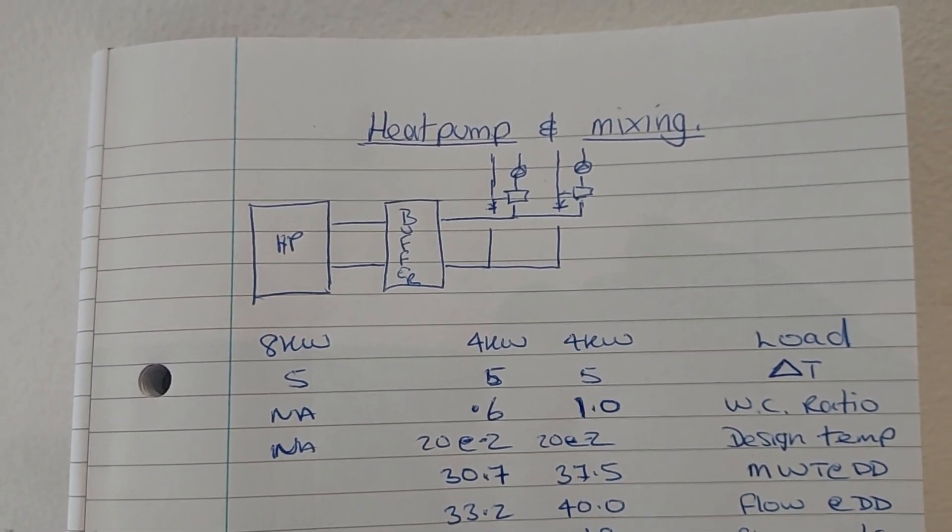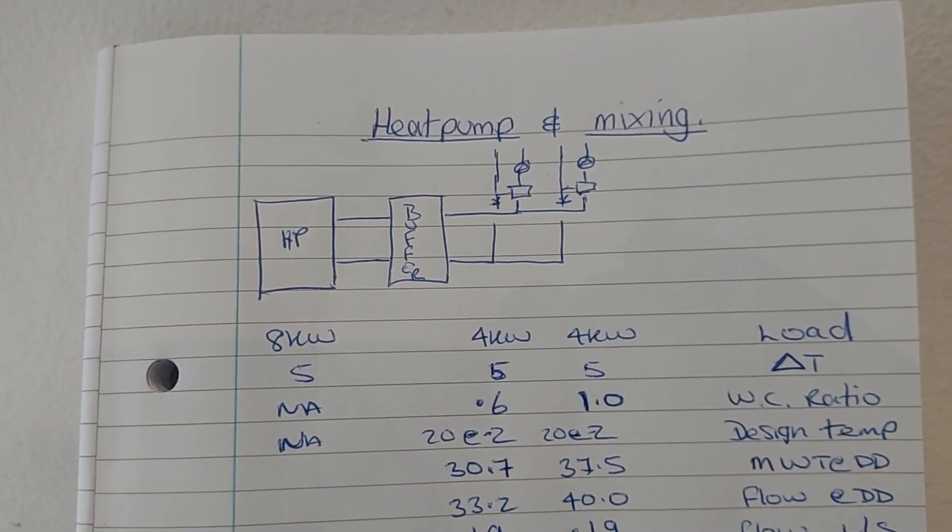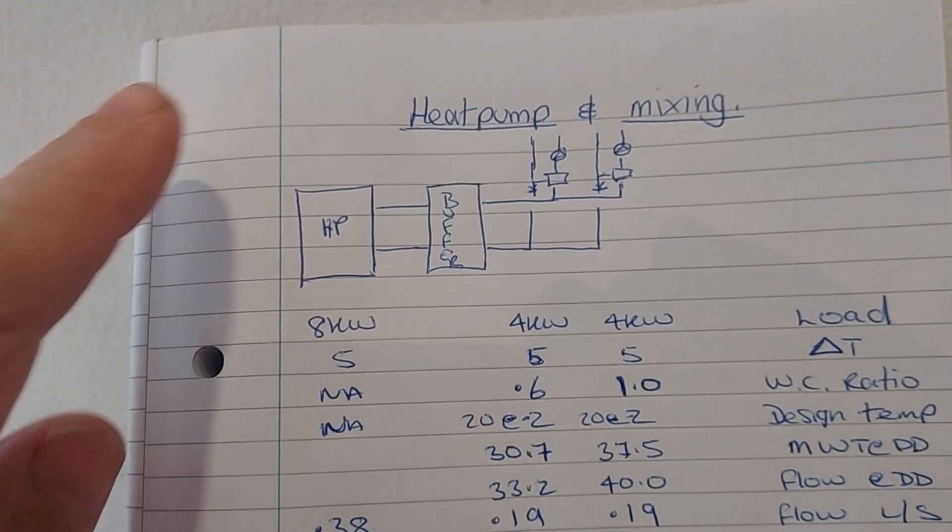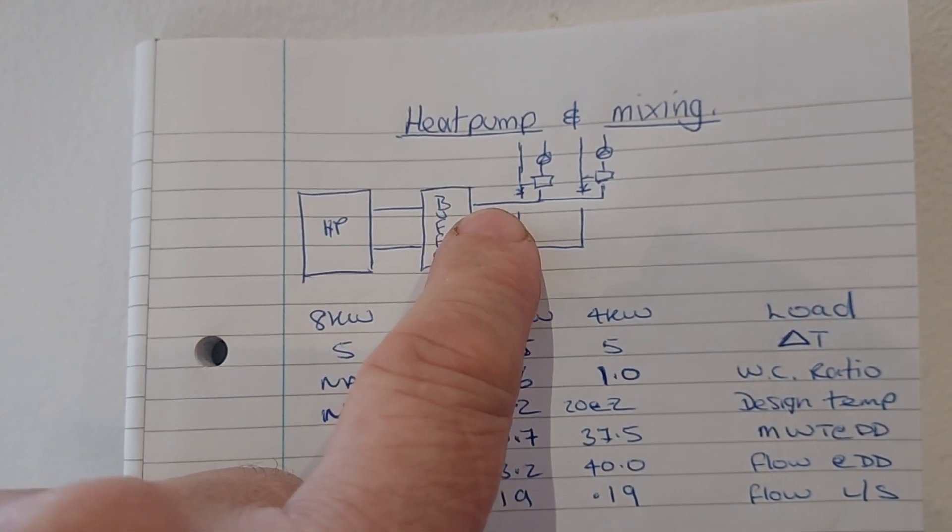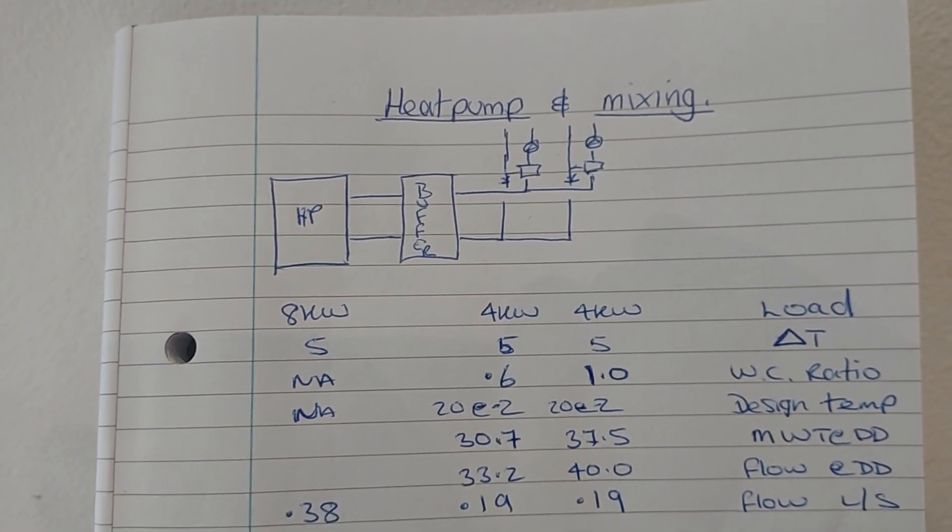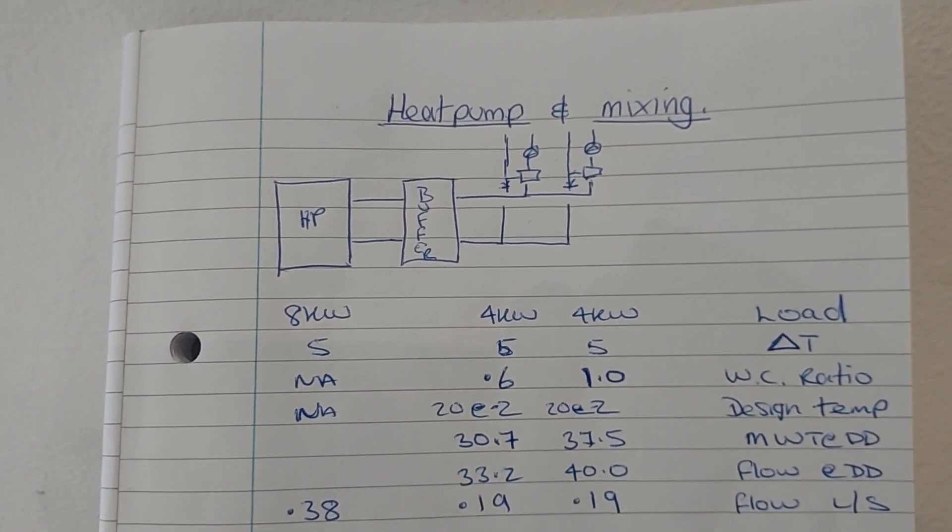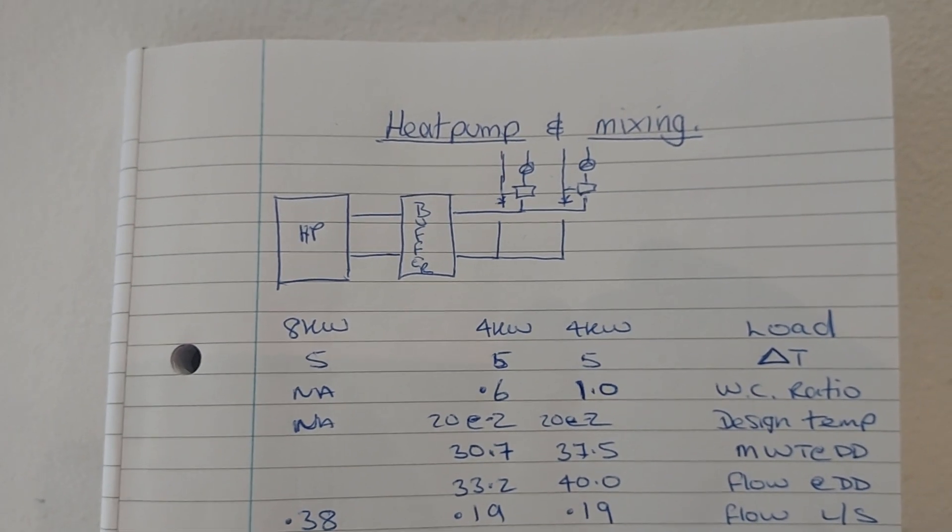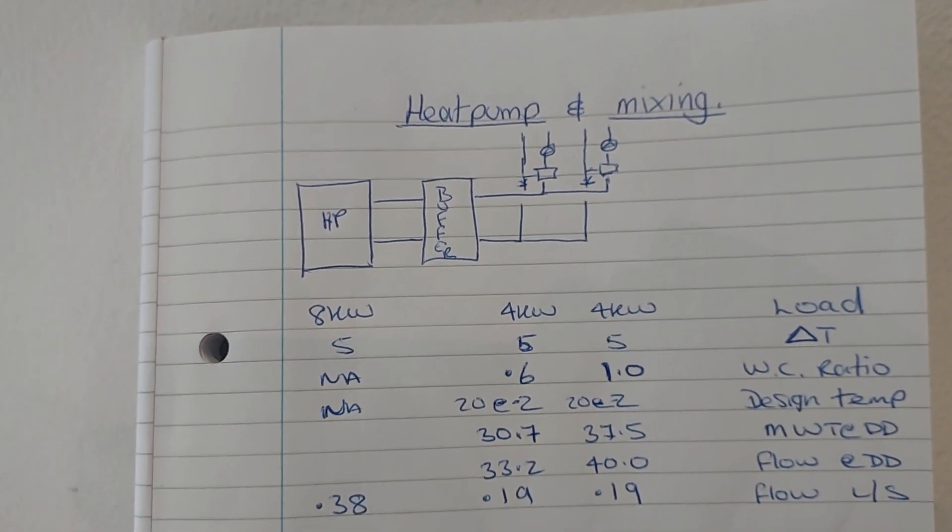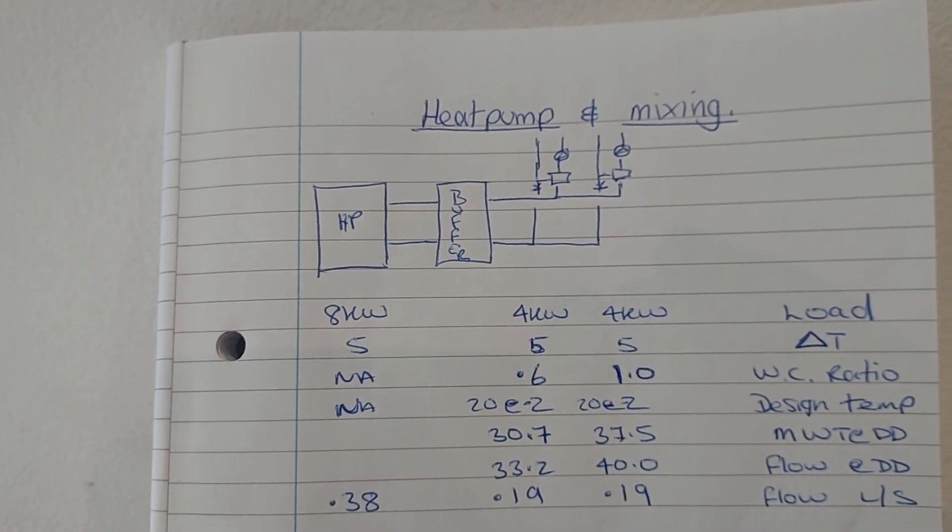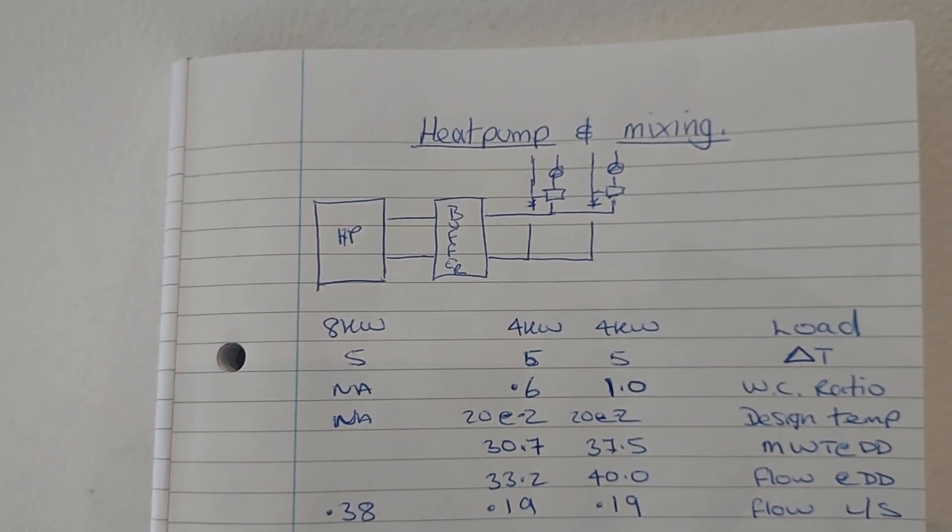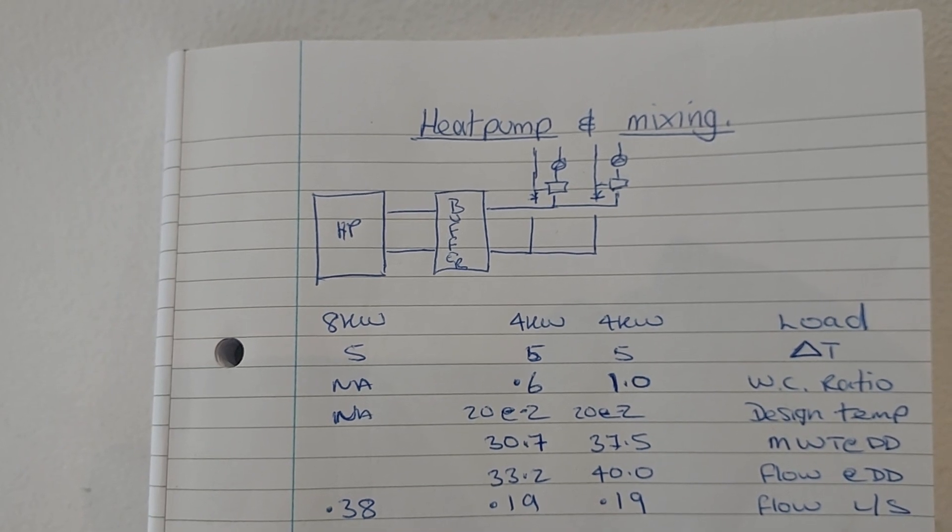I've shown these both with variable-temperature mixers, not high-temperature mixers. But if you've got a good control system, you would have a buffer sensor or a secondary flow sensor here, which would probably make one of the mixers redundant. Quick note on here, this is on a heat pump, not on a gas boiler. On a gas boiler, you will invariably need to have a mixer on both circuits. But for a heat pump, there's a good chance that your radiator circuit would not need a variable-temperature mixer.